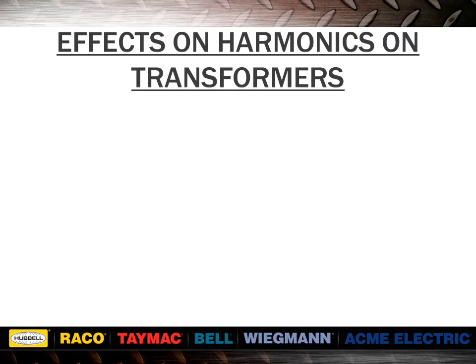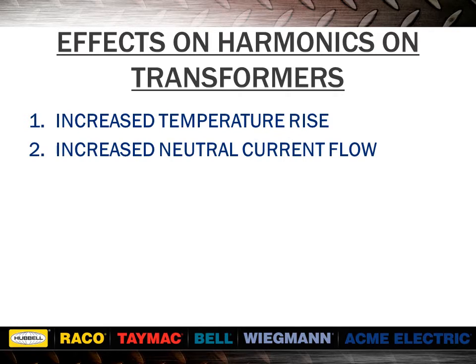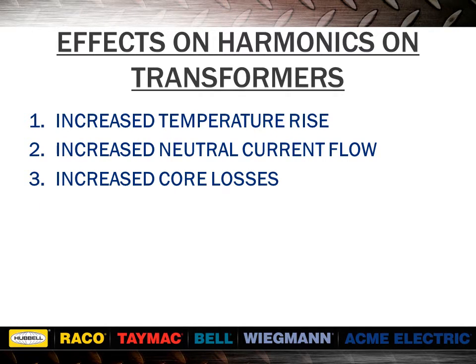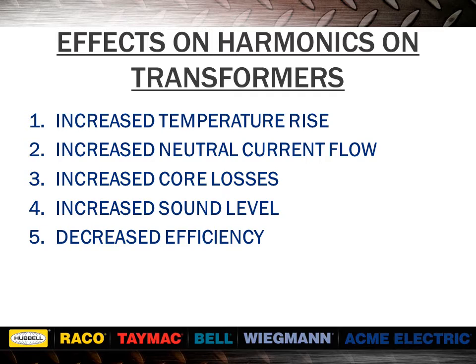The effects of harmonics on transformers include increased temperature rise, increased neutral current flow, increased core losses, increased sound level, and decreased efficiency. Stray losses in the conductors get multiplied by the k-factor of the load to increase winding rise. Triplen harmonic currents add up in the three-phase neutral, and harmonic voltages tend to increase losses in the iron core.